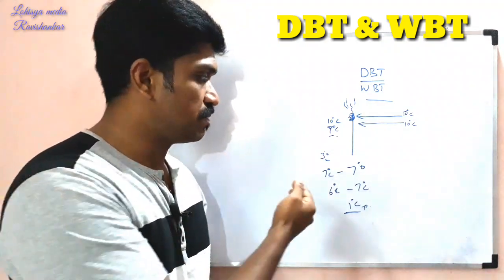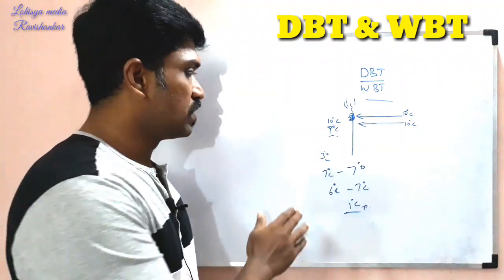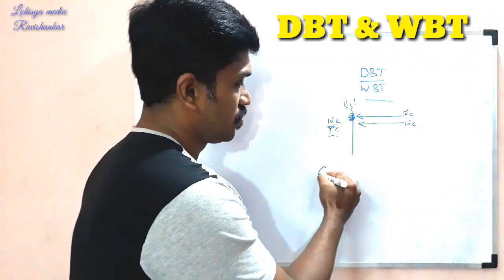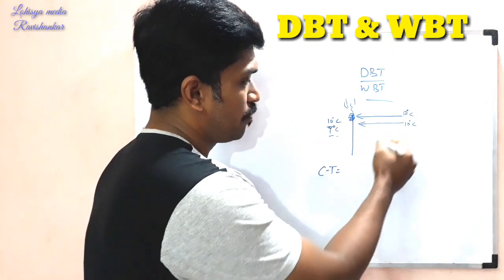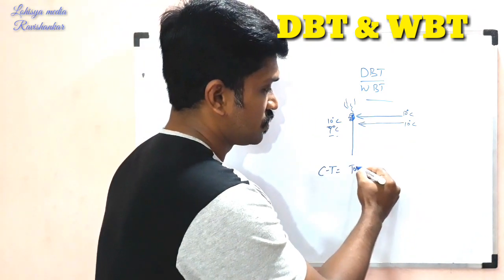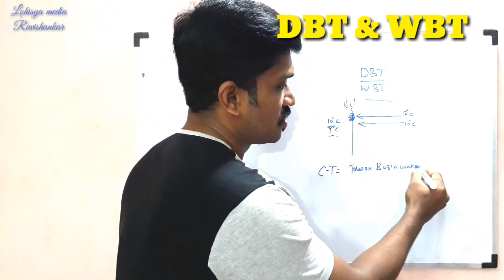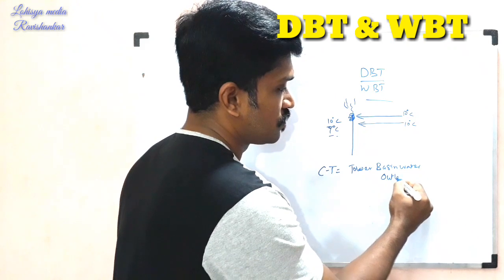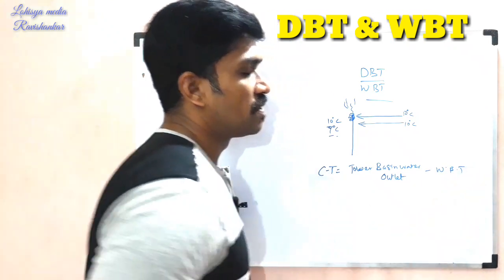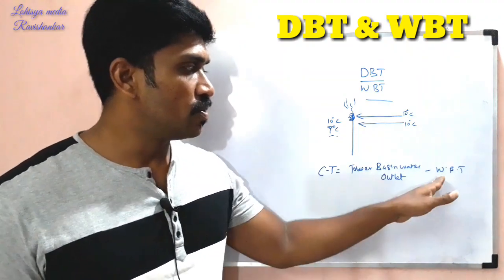What is the substance? How do you say this in a cooling tower? Cooling tower approach equals basin water outlet minus wet bulb temperature. That is the formula. The wet bulb temperature is subtracted from the basin water outlet temperature to give the cooling tower approach.